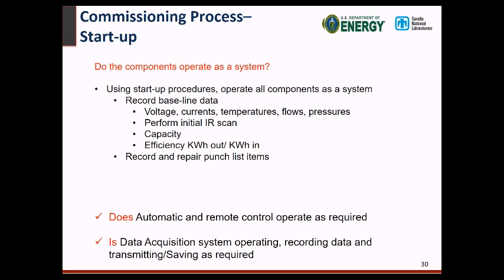You also want to do a capacity test. This is charging the system up to 100% state of charge and back down to 0% state of charge, at either 100% depth of discharge or at different ratings, and you're looking at the capacity. You want to do this about 3 times, and this will give you a baseline of what your system is, and make sure it meets your performance specs. That if you bought a 1 megawatt hour energy storage system, you're getting a 1 megawatt hour energy storage system.